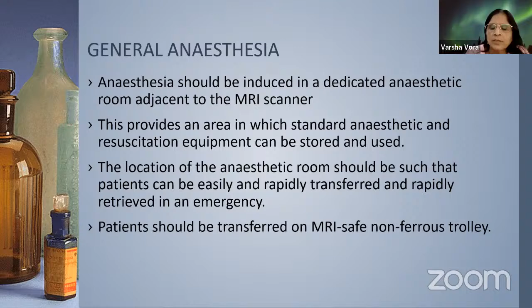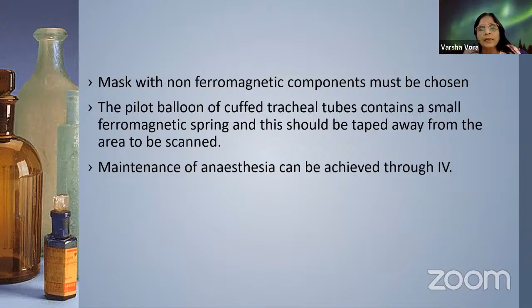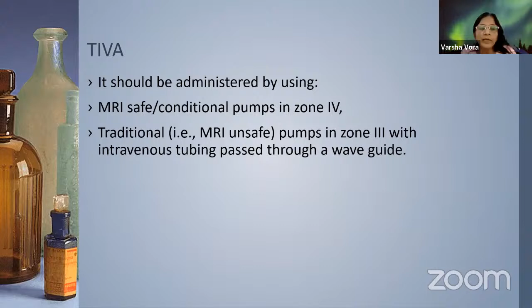The pilot balloon of a cuffed endotracheal tube contains a small metallic spring, and this should be taped away from the area to be scanned. That's why many times an LMA or I-gel is used to avoid this. Maintenance of anesthesia can be achieved through IV TIVA. It should be administered using an MR-safe or conditional pump in zone 4, and traditional MR-unsafe pumps in zone 3 with intravenous tubing passed through a waveguide, or given slowly IV, very much diluted.